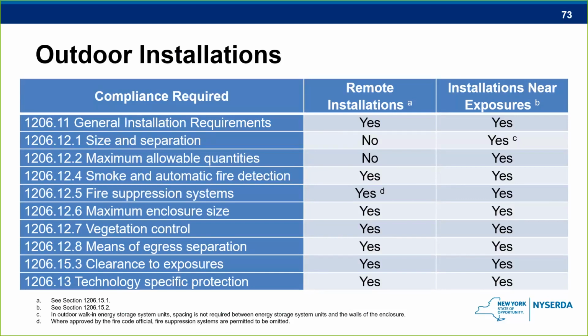Note the subscript on the suppression system line here, which is about halfway down the slide. The AHJ, the authority having jurisdiction, can allow the suppression system to be removed in this situation for remote installations. And again, that's due to the lower risk of actually hurting someone if an incident were to occur.